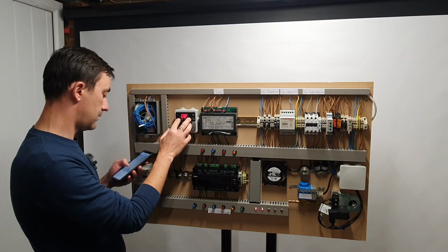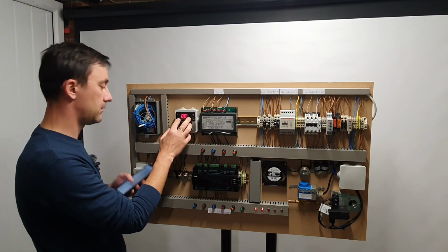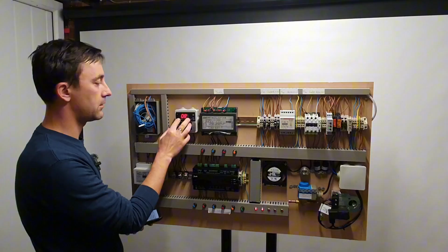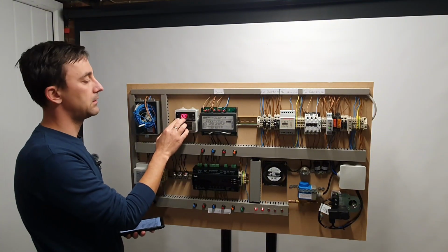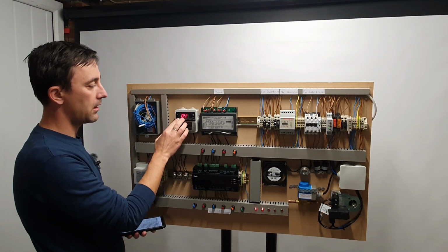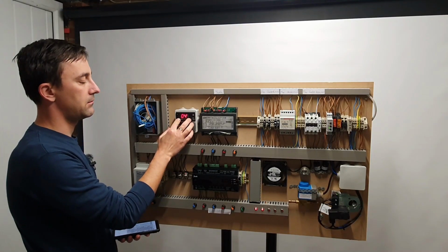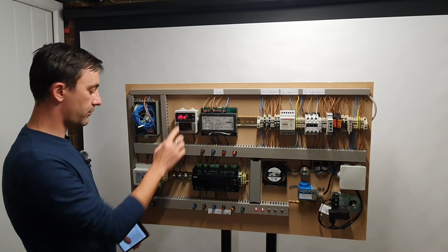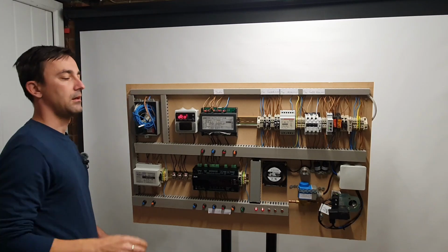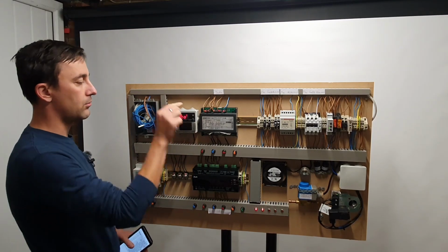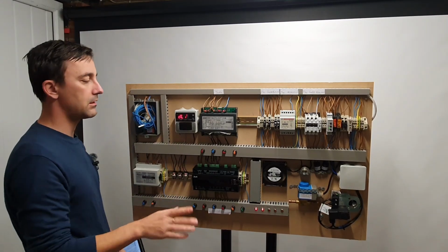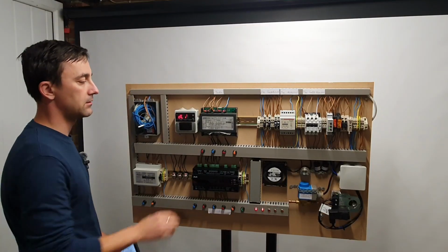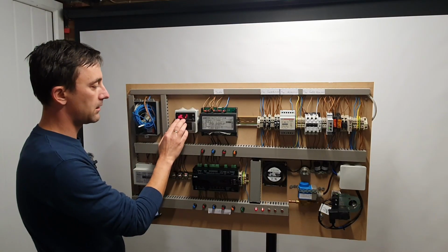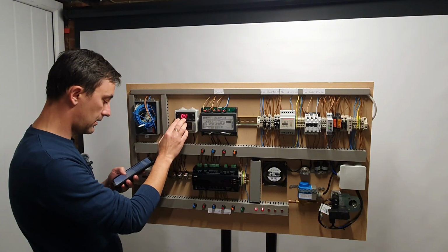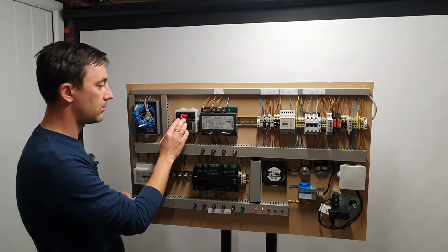DLI is the defrost end temperature. Yes, it's the defrost end temperature set at 8 degrees. I think that's a bit high. I would set this to 4 degrees. The idea behind it is, if your defrost probe, which is this one, being stuck inside the evaporator or one of the passes, if it's reading 4 degrees, that means you got rid of all the ice built up.